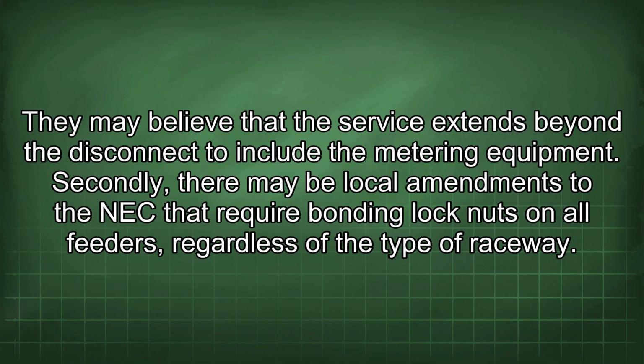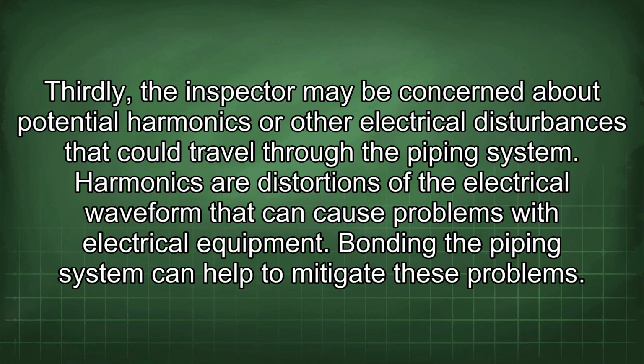Secondly, there may be local amendments to the NEC that require bonding lock nuts on all feeders regardless of the type of raceway. Thirdly, the inspector may be concerned about potential harmonics or other electrical disturbances that could travel through the piping system. Harmonics are distortions of the electrical waveform that can cause problems with electrical equipment. Bonding the piping system can help to mitigate these problems.